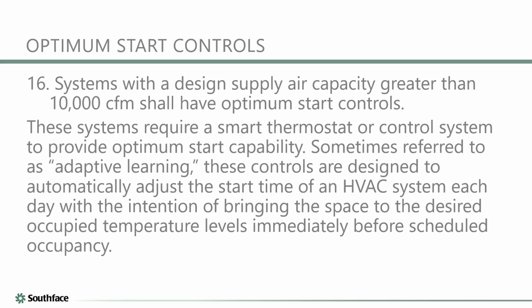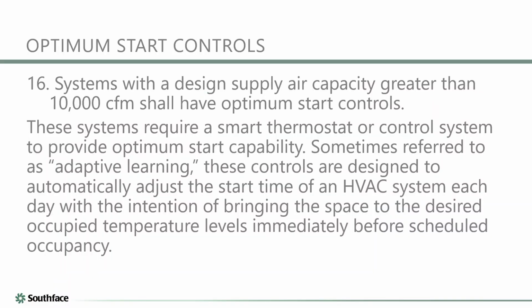Another requirement, optimum start controls. Systems that have more than 10,000 cubic feet per minute of supply air capacity are required to have these smart controls. And this is basically just a type of control function in the thermostat that allows it to learn how you use the building and to adjust when it brings the equipment online so that it aligns with when you're going to need the space conditioned.